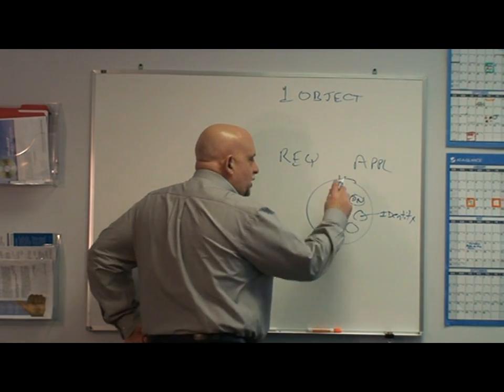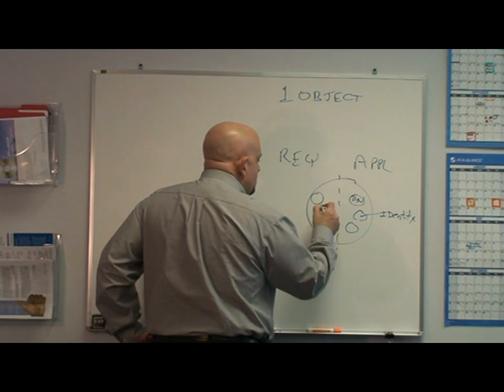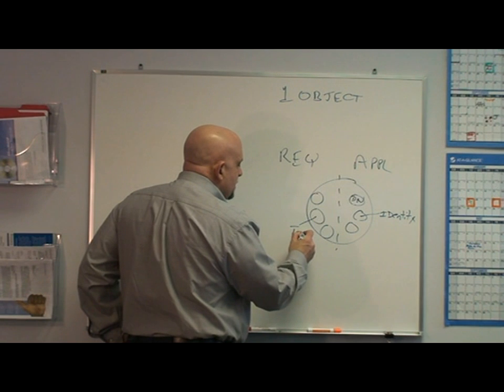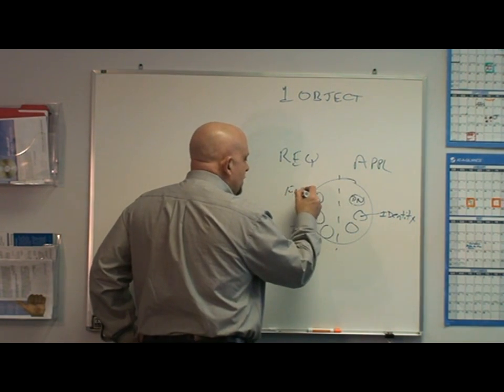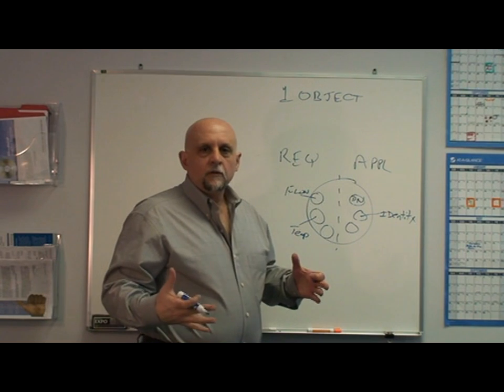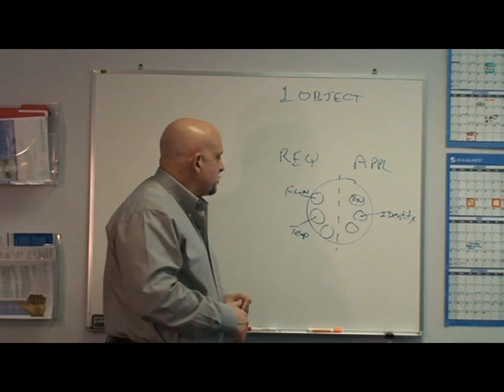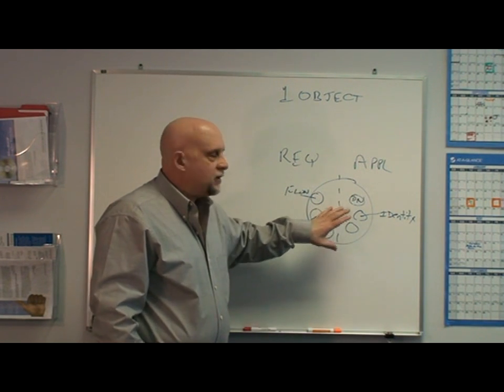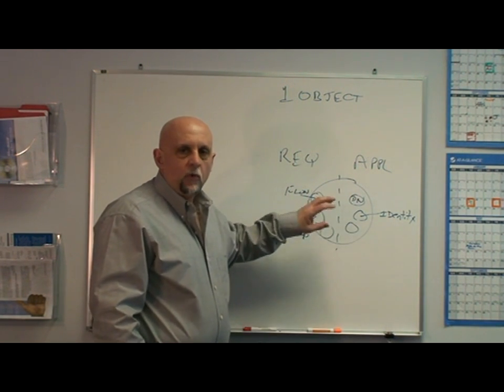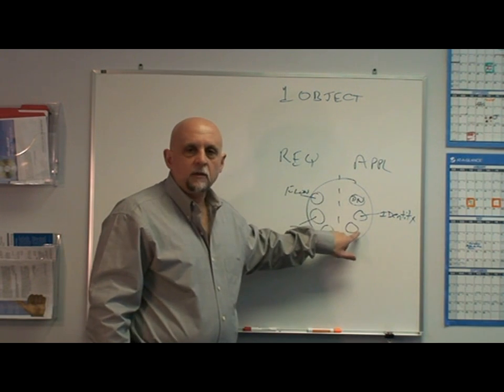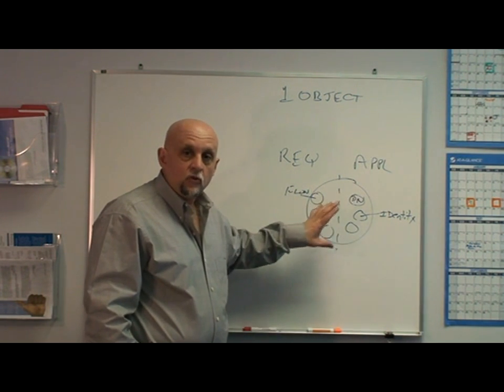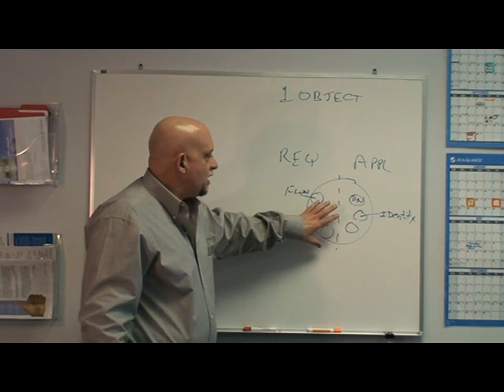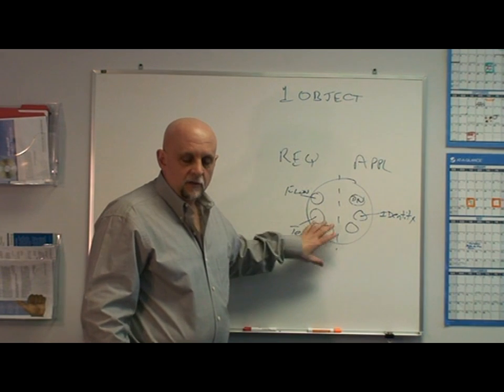Those are required objects. You also have application objects. If you're implementing a flow controller, you might have a temperature object that holds the temperatures you measured, and a flow object that has the current flow being measured. You organize your data in a DeviceNet device in terms of objects with attributes for each data item. That's not how you do it in software — in software you can do it any way you want. It's just the representation to the network that is object-based.